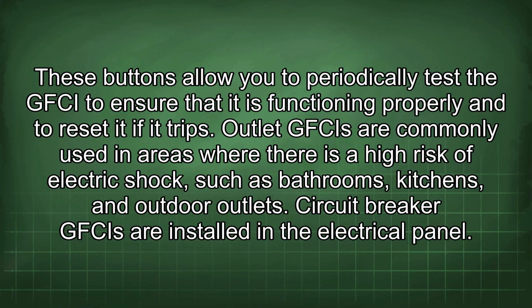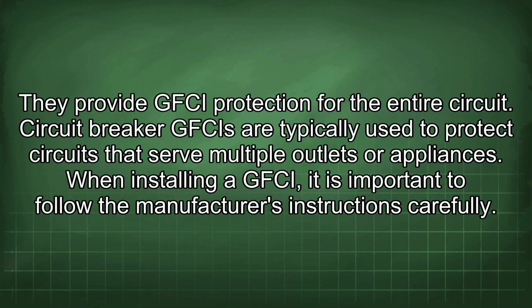Outlet GFCIs are commonly used in areas where there is a high risk of electric shock, such as bathrooms, kitchens, and outdoor outlets. Circuit breaker GFCIs are installed in the electrical panel. They provide GFCI protection for the entire circuit. Circuit breaker GFCIs are typically used to protect circuits that serve multiple outlets or appliances.